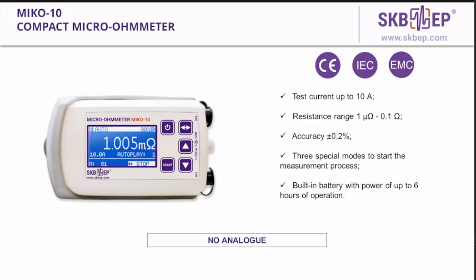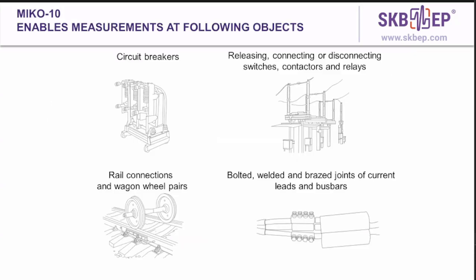MIKO-10 enables stable and accurate measurement of the contact resistance of different circuit breakers, releasing switches, relay contacts. It is as well suited for measurement of different detachable and non-detachable connections located on a small territory. Besides, the instrument is also used at the railways for resistance measurements of rail connections and wagon wheel pairs.